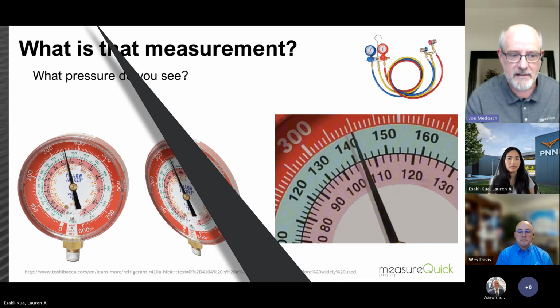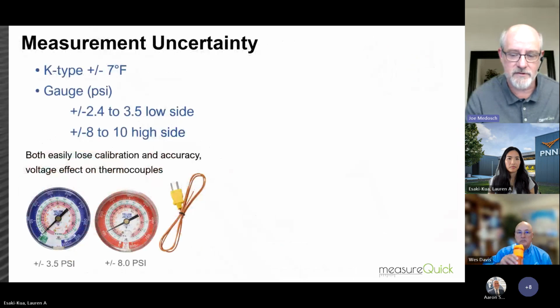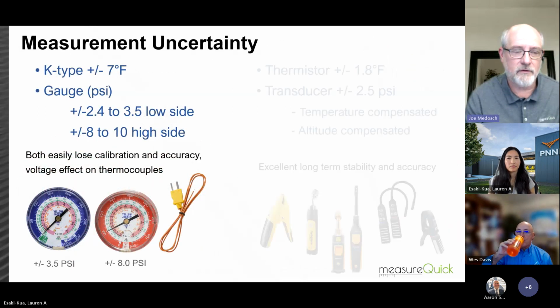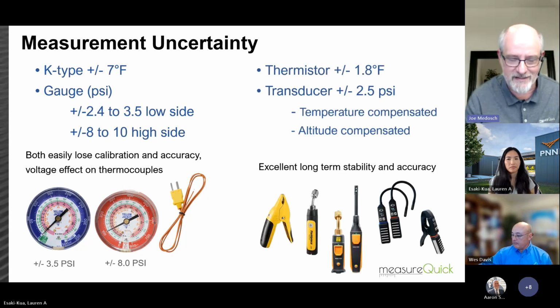So you can see where these things have actually gotten us into a lot of trouble in terms of critical measurements—there's a huge margin of error involved. I actually took a few slides out because I was worried about time, but you're looking at readings of plus or minus 3 or plus or minus 8 psi, and how that gets extrapolated in these K-type measurements for your temperatures, plus or minus 7.